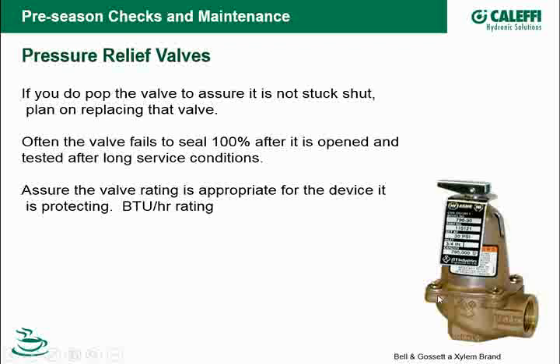Keep in mind, if you pop this valve, there's a chance that the valve's not going to seal again after you release the handle, because you can rip that little diaphragm or that little washer that's in there if you pop one that's been stuck for a while, and then they're going to seep through there, and then you're going to have a drip. So if you are going to go around and pop these valves when you do a check, and I know this happens a lot when home inspectors go around and do a home inspection on a boiler or something like that, and they say, oh yeah, my checklist says to pop the relief valve on the water heater or the boiler, and then they drip from that day forward. So if you're going to do that on a check, I would make sure that you've got a valve with you to replace it. Make sure you've got the right size and the right capacity. So if that valve doesn't seal again after you pop it, you've got one that you can replace quickly.